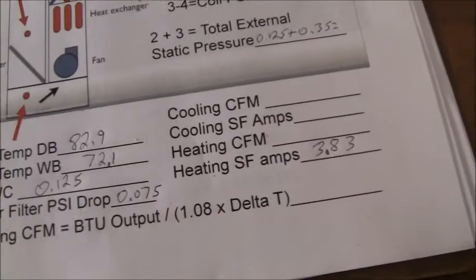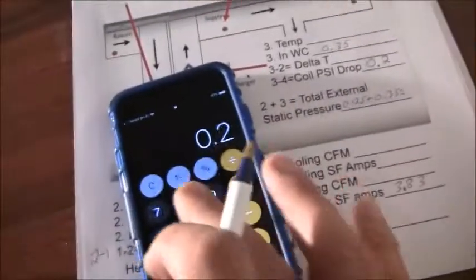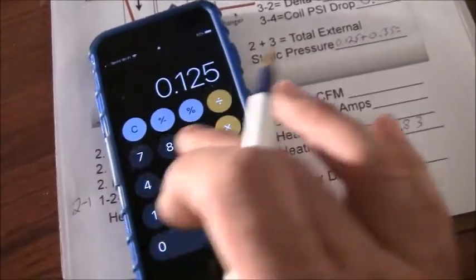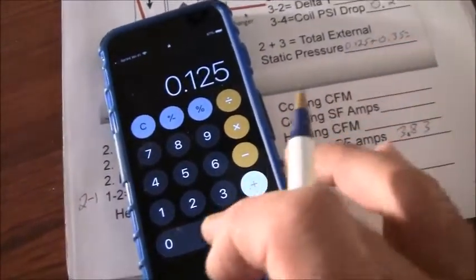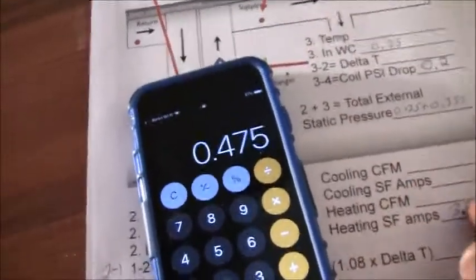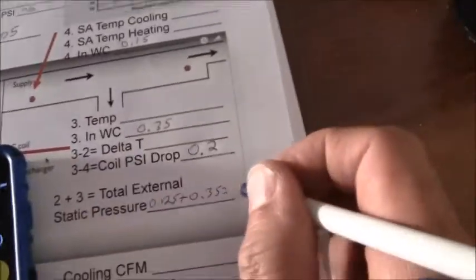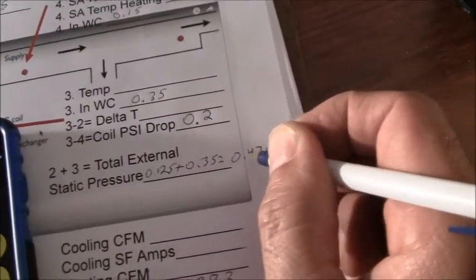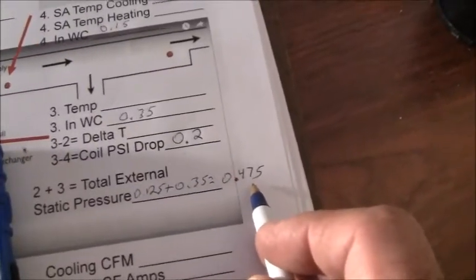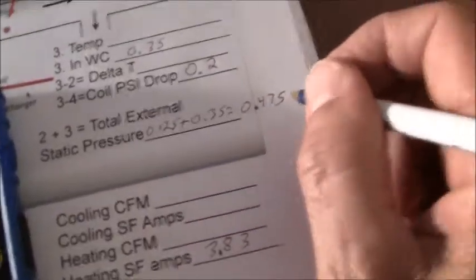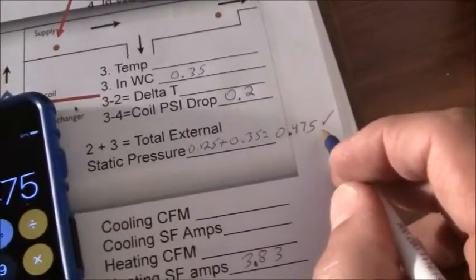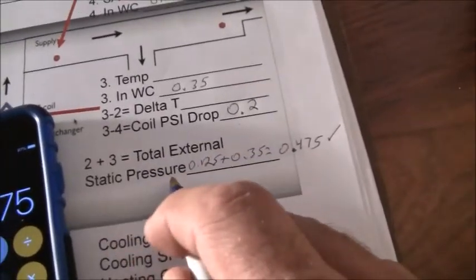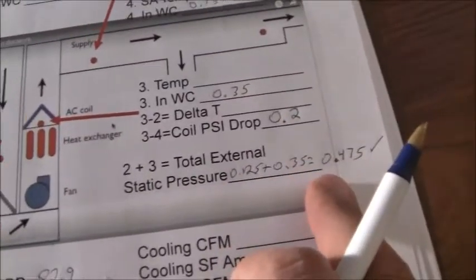Okay, let's go ahead and get that going. 0.125 plus 0.35 equals 0.475. Now my unit did not have a rated external static pressure, but if you're at a 1/2 inch or less, which is what I am, that is considered good. I don't have a restricted airflow from a total external static pressure point of view, which is how you want to review this.